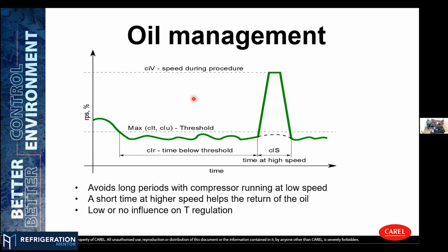And this is one of the features we implemented into our software. Basically, when the compressor starts to run at a very low speed, we can define a threshold for that, and for a long period we force the compressor to run at a higher speed to make the oil drag back from the evaporators or from the system to the compressor. This can be done in parallel with the electronic expansion valves when they are connected together. So we can open the valves a little bit and accelerate the compressor in order to drag all the oil back from the system to the compressor.